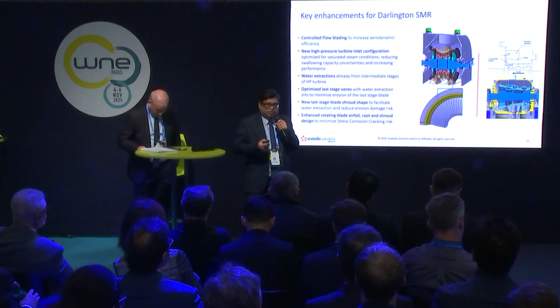Whereas fossil, you can just increase the flow a bit by building more cold flow. But here the thermal capacity is same, so the swallowing capacity needs to be ensured. And that's why we made that change. Also, the steam condition is wet at the beginning. So once it expands, in this area, quite a lot of coarse droplets you will find. And it's important to prevent the erosion by taking those droplets out of the flow path.